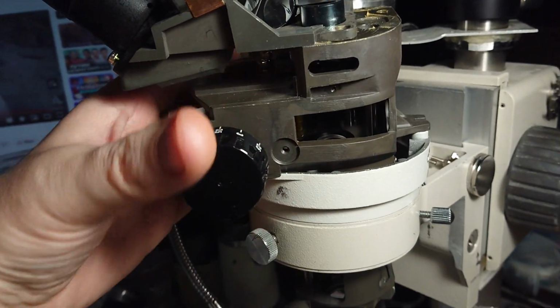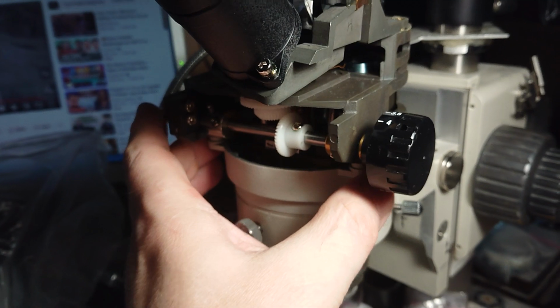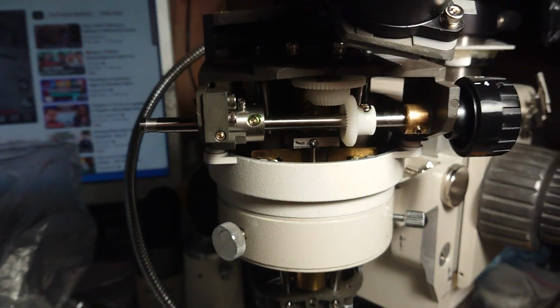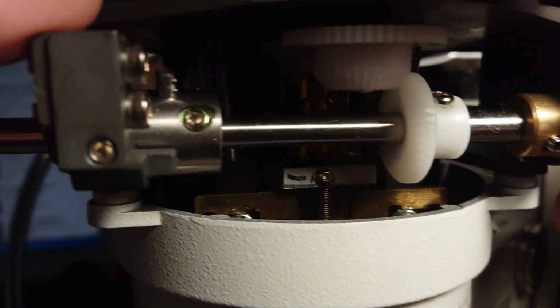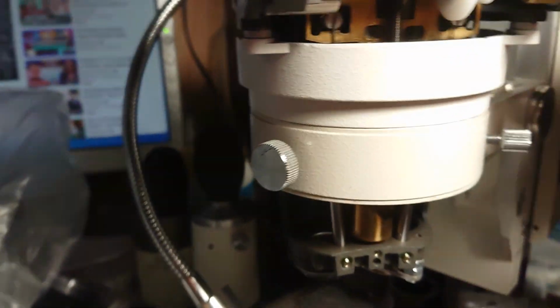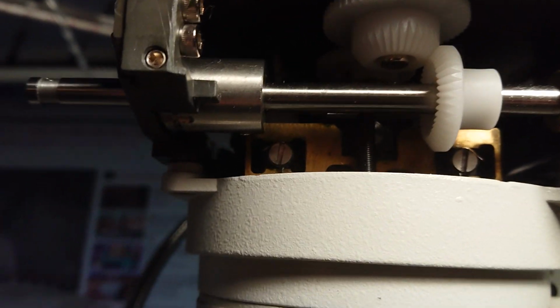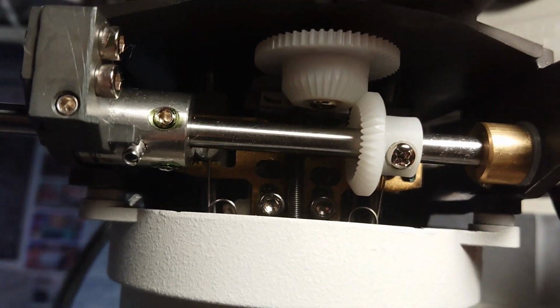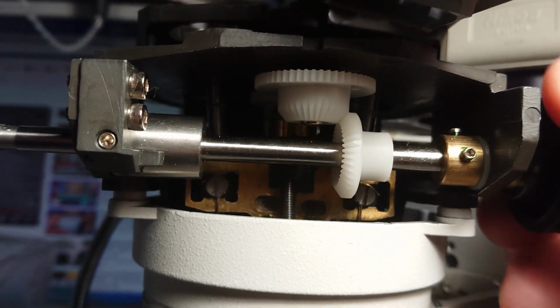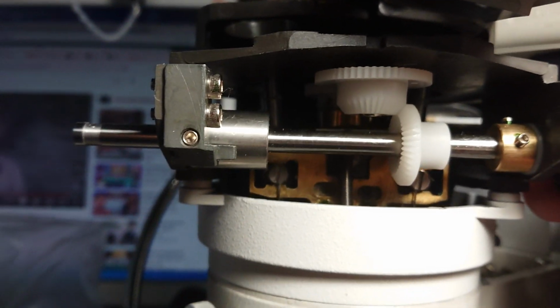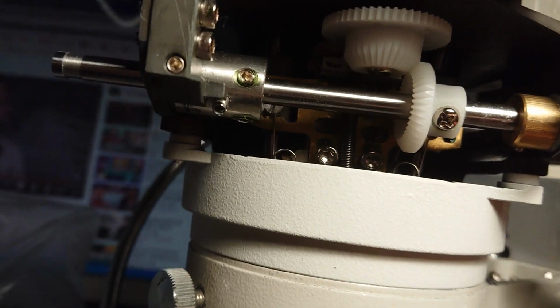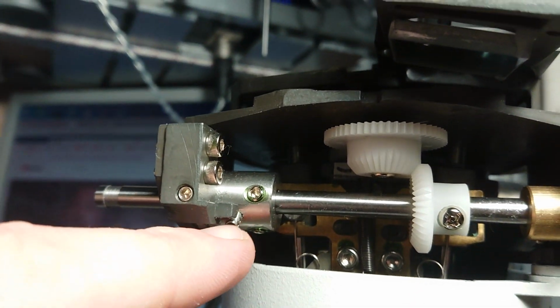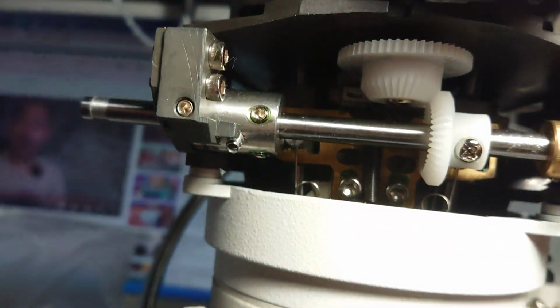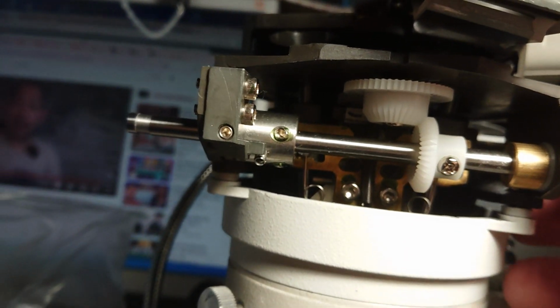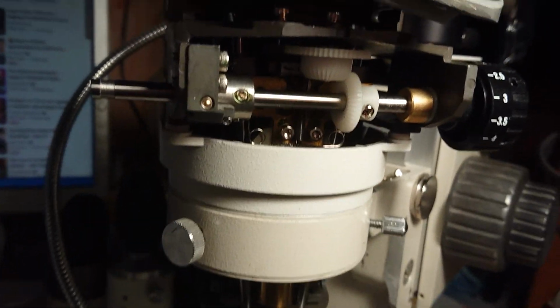So it's the last thing I have to finish, when this microscope will have a pretty increased resolution. And by the way, for those who want to increase the magnification a bit, you can take this part, it's a limiter. When this thing rotates, it limits the way of the zooming system in both directions. So if you want to make the zoom range a bit higher, you need just to cut away a bit of this pin. If this pin is cut away, you can get a little more zoom range. It might be pretty useful for some applications.